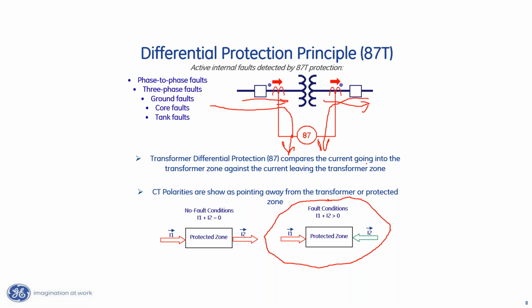If I don't have a source out here, then I don't have this current, right? So this current I'm Xing out right here. And if that's the case, I've got 10 at 0 degrees on this side, and 0 on the other side. So 10 at 0 and 0 at 0, when I vectorially sum those, that's 10 at 0. That's differential current. That would cause me to operate. So, at its basic core, that's what differential is, and that's how differential works.